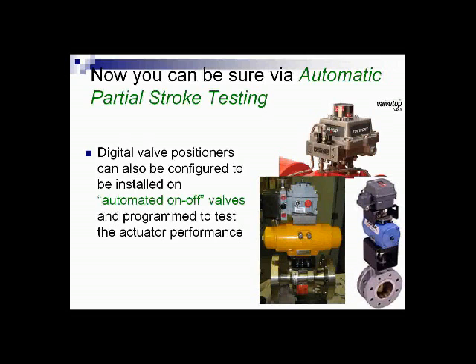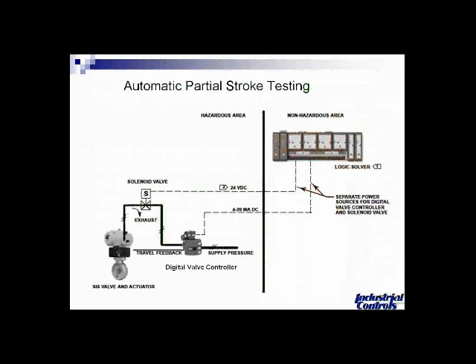The next slide is going to give you a schematic of how this actually works. To the right up here is your programmable logic controller. This is set up to, on a timed basis, send the signal out to the digital controller, and if this valve essentially was open all the way, it would hit this solenoid valve to exhaust some of the air out, and it will take that valve from full open maybe down to about 70% open. And then it would look at a lot of different factors while it's doing that: how well that moved, whether it's stuck or not, whether there was a delay when the air exhausted. And it gives all that information back to the controller and actually tells you the health of that valve.